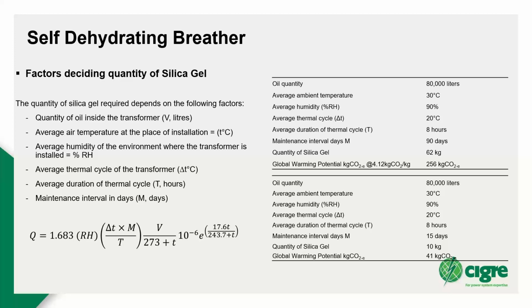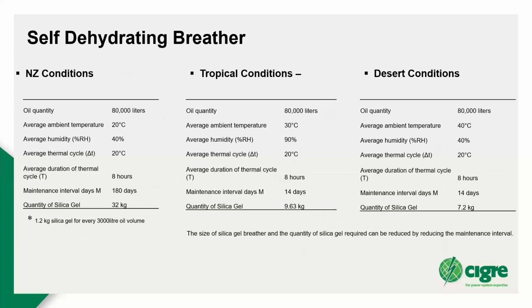10 kgs will dramatically reduce the carbon footprint from almost 250 kgs to 41 kgs. So depending on conditions, how often you want to maintain the silica gel, the size of the breather, the quantity can be reduced by reducing the maintenance interval.